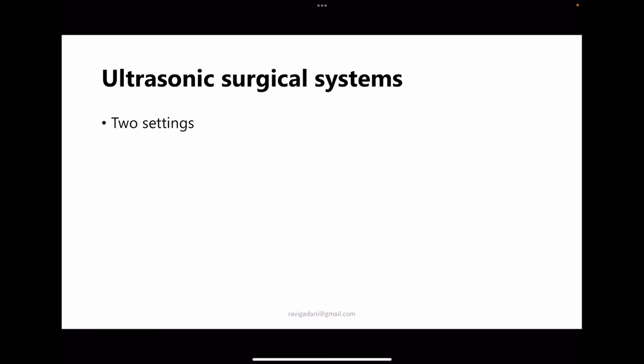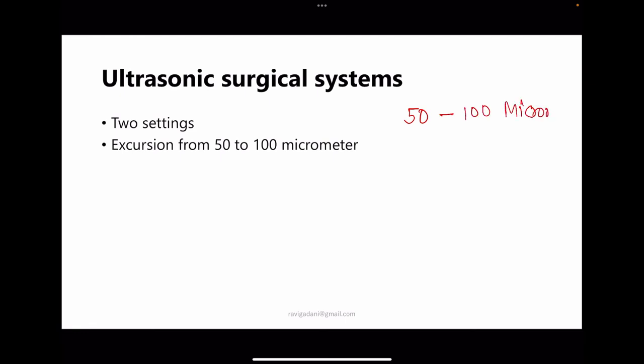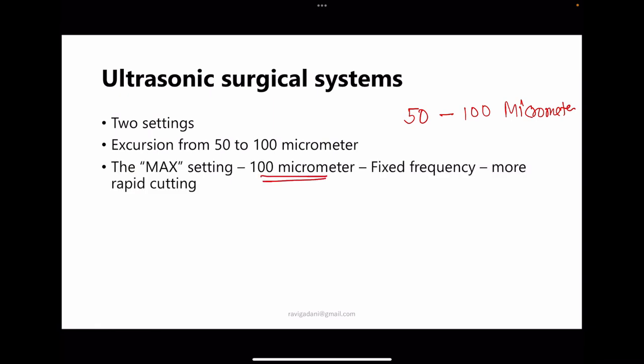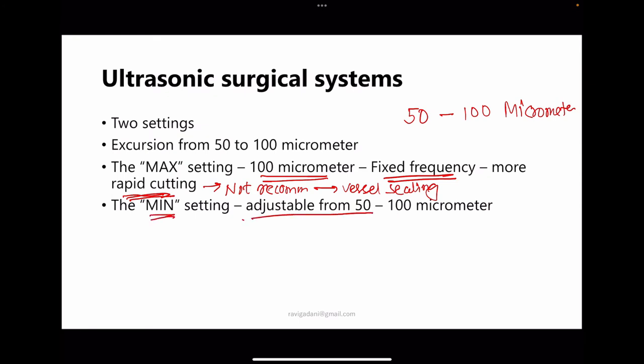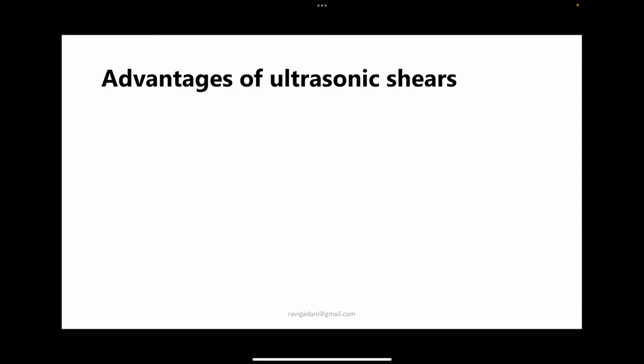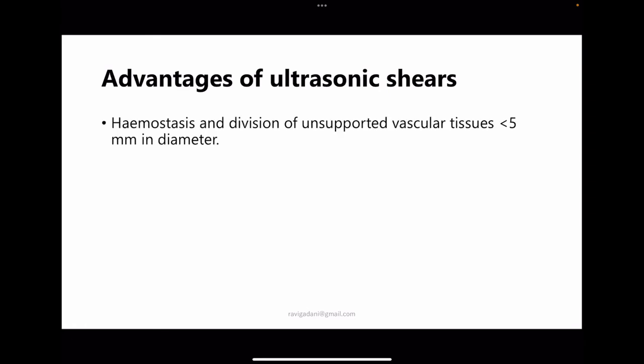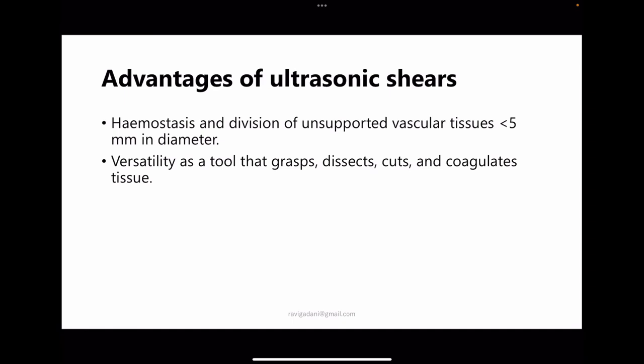Ultrasonic surgical systems typically have two settings, with excursions of 50–100 micrometers. The max setting at 100 micrometers gives fixed frequency and more rapid cutting but is not recommended for vessel sealing. The main (adjustable) setting is recommended for vessel sealing. Advantages include hemostasis and division of vascular tissue up to 5 mm in diameter, versatility as it grasps, dissects, cuts, and coagulates. It also cuts tissue — unlike some bipolar devices that require a separate scissor after coagulation.